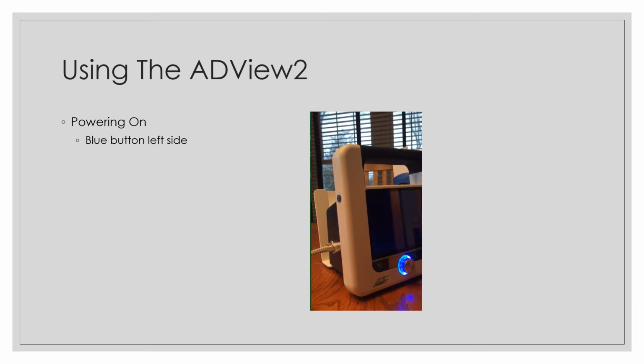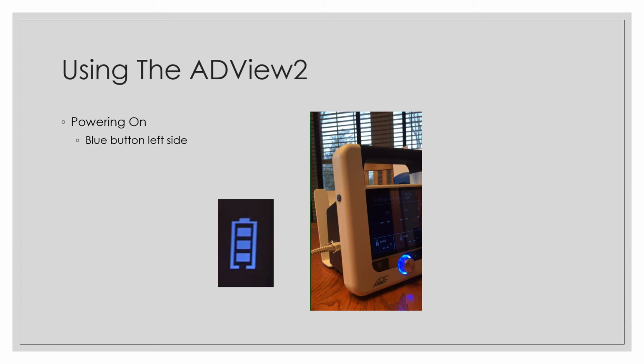The unit is on or in sleep or standby mode whenever the blue ring around the selection control knob is lit. Remaining battery life is indicated by the number of bars showing in the battery charge icon. At a full charge, all 3 of the bars will be illuminated. A full charge should enable you to take up to 200 separate vital sign readings. When the remaining battery charge is down to a single bar, between 11 to 40% of battery power remains. At this point, the unit should be plugged into a 110-volt outlet for recharging as soon as possible.